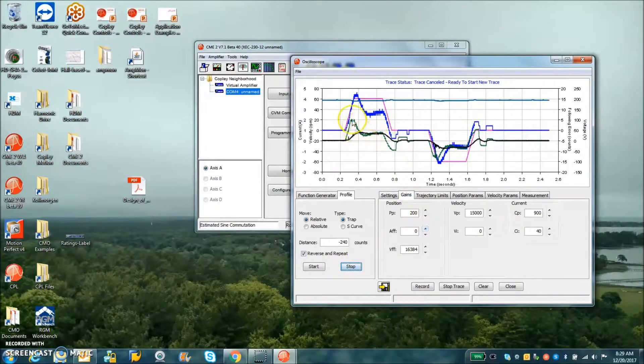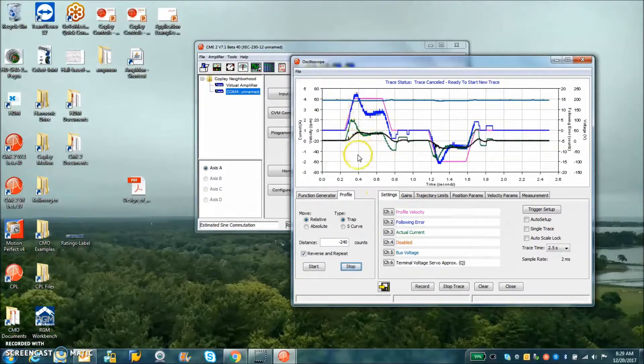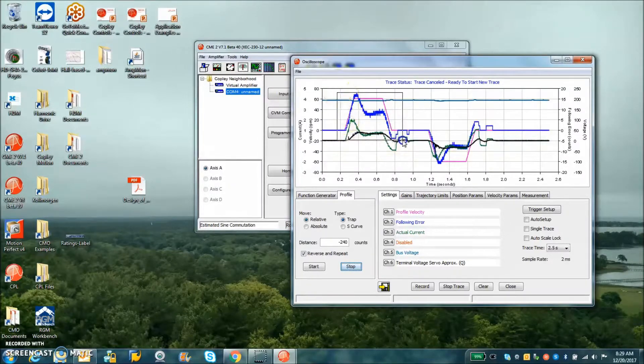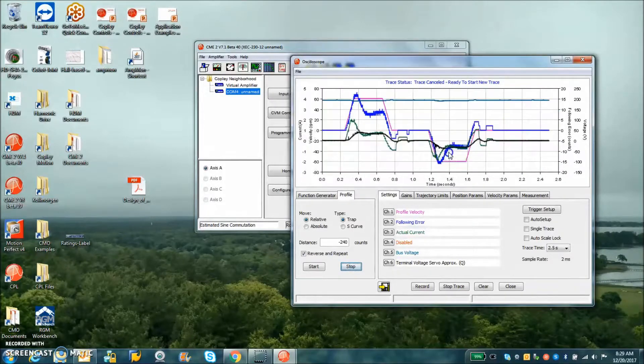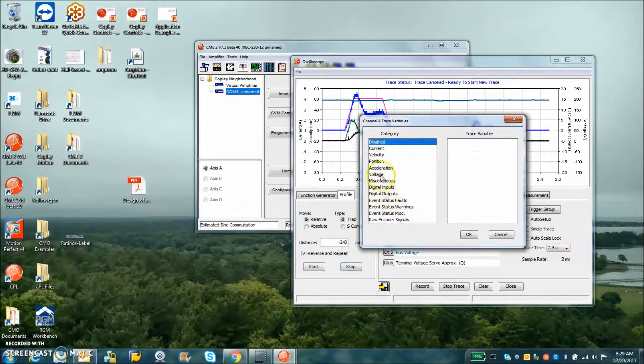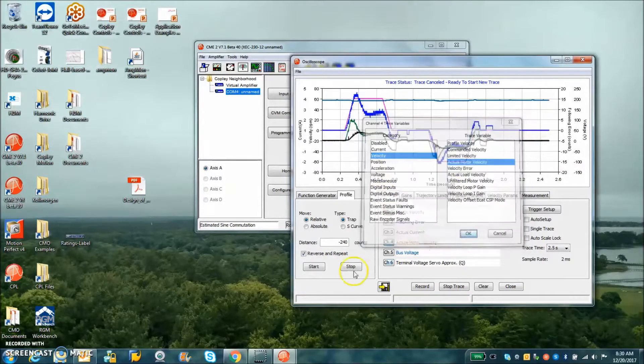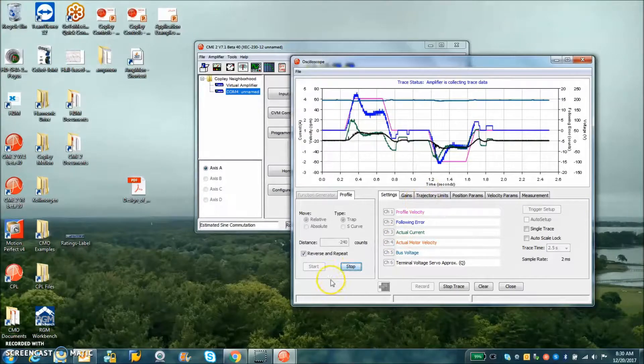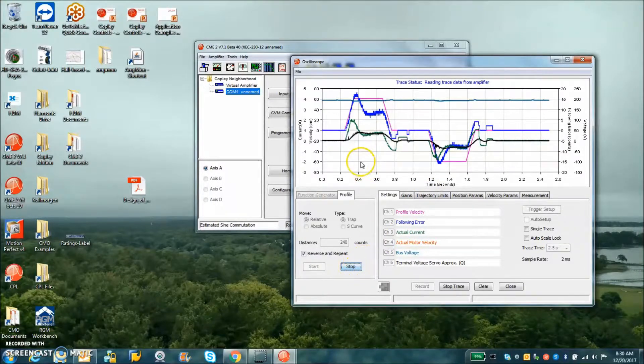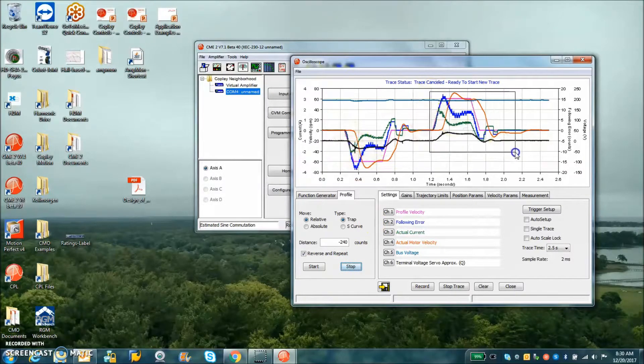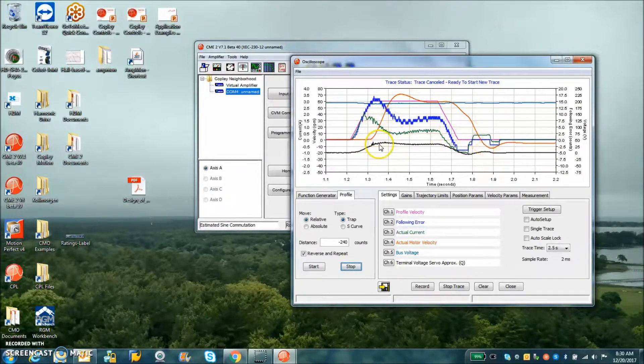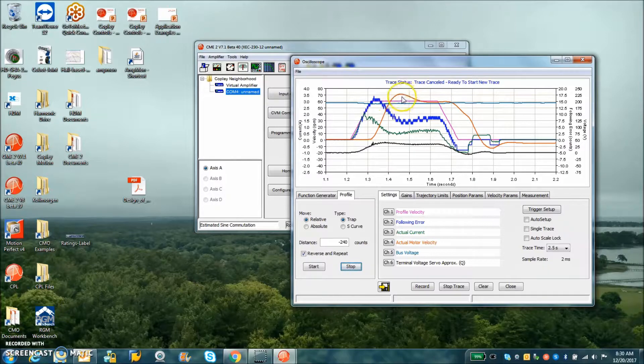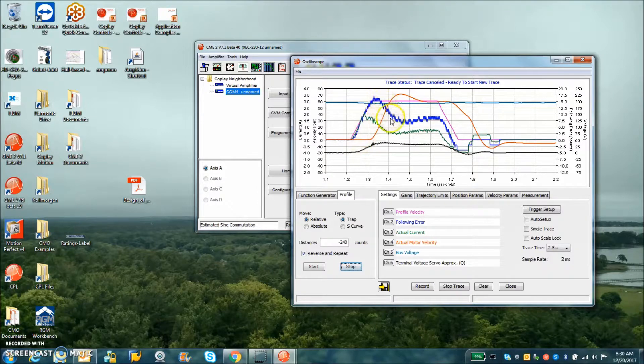I've got the gains for the position loop down a little bit. We can see the profile velocity accelerate, run, decelerate, stop. We could monitor the actual velocity. The profile accelerates, decelerates and stops. The actual velocity is shifted over a little, overshoot gets to steady state, the following error increases a bit while we accelerate, levels out.